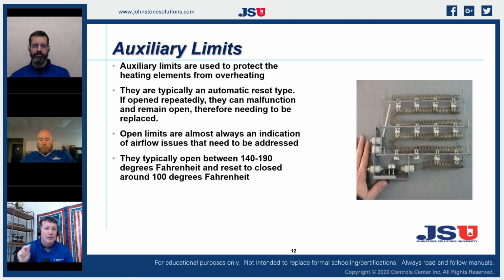So when we have that complaint, hey, my electric furnace's blower is running all the time, and the heat is cycling on and off every 5-10 minutes, that is telling us that our auxiliary limit has been opening and closing, and it's not supposed to. It's supposed to be there as a safety device. So if we have one that has been opening and closing routinely, I recommend replacing it as a service part. They're very inexpensive, and they were there to be a safety device, not an operating device. They were never designed to be a functioning part of that system, not a regulating part. They're supposed to be there as an emergency function. So if we have a dirty filter, a plugged coil, or a plugged blower wheel that's been causing that limit to reset regularly, it's time to change that thing and put a new one in.